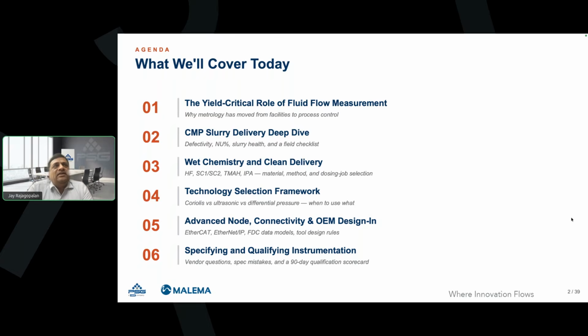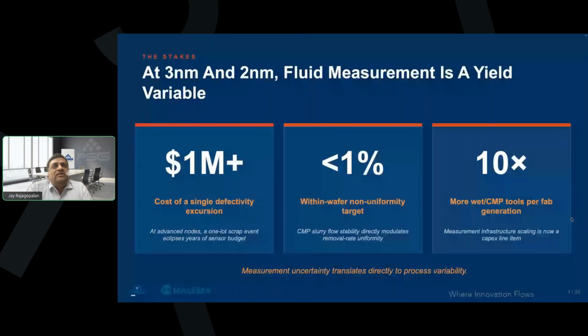What is at stake? When you consider the advanced nodes like 3 nanometer and 2 nanometer, the fluid measurement is a yield variable. And also, if you look at the defectivity that might occur in the fab, one lot scrap event due to a defect can cost millions of dollars, and at least a million plus, which itself eclipses the whole cost of the sensor for an annual budget for a fab. So that means it's so critical to select the right flow technology for the right application.